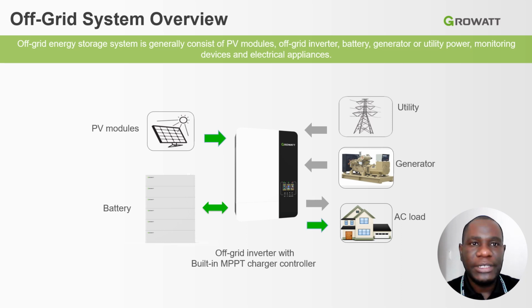Here is an off-grid system overview, which consists of, on the DC side, the PV input, which is PV modules, and we have the DC input from the batteries. On the AC side, inputs, we have the utility, the generator is an option, and we have the load, of course, and our off-grid inverter in the middle. That picture is showing you how the SPF 5000 ES inverter looks like. And please take note that this off-grid inverter has got a built-in charge controller, which is an MPPT type.